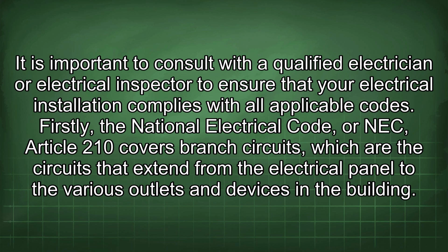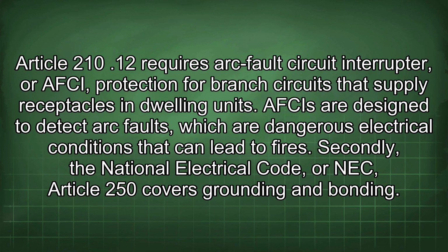It is important to consult with a qualified electrician or electrical inspector to ensure that your electrical installation complies with all applicable codes. Firstly, the National Electrical Code, or NEC, Article 210 covers branch circuits, which are the circuits that extend from the electrical panel to the various outlets and devices in the building. Article 210.12 requires arc fault circuit interrupter, or AFCI, protection for branch circuits that supply receptacles in dwelling units. AFCIs are designed to detect arc faults, which are dangerous electrical conditions that can lead to fires.